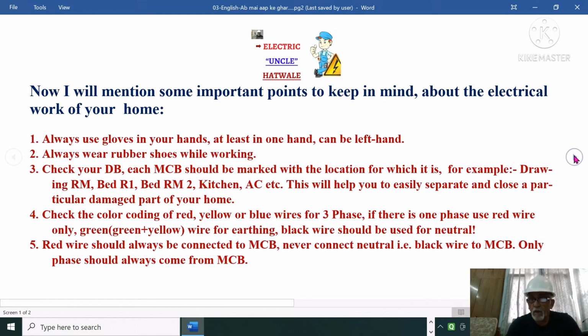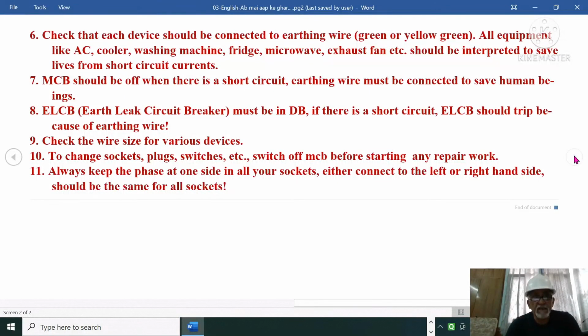Next, number 6. Check that each device should be connected to the earthing wire, green or yellow-green. All equipment like AC, cooler, washing machine, fridge, microwave, exhaust fan, etc. should be earthed to save lives from short circuit currents. On this slide I was in a hurry, so I will change it. When you find it in the PDF, it will say should be earthed to save lives from short circuit currents. MCB should be off when there is a short circuit. Earthing wire must be connected to save human beings.